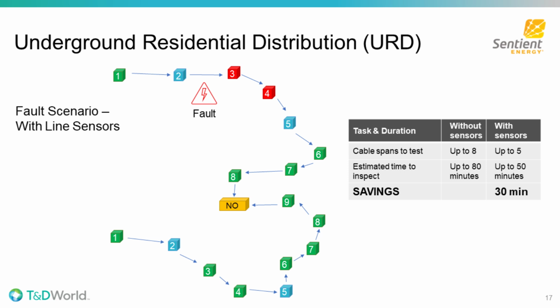The third piece I'd like to highlight is the use of loading information to confidently close the normally open point during an outage. For example, in this circuit map URD loop, if you have an outage out there and you want to close the normally open point to feed from the other direction, knowing how much the load was before the fault happened lets you know that closing it in won't trip the fuse on the other side or take more people out of power. At times, this can also lead to a safety issue.